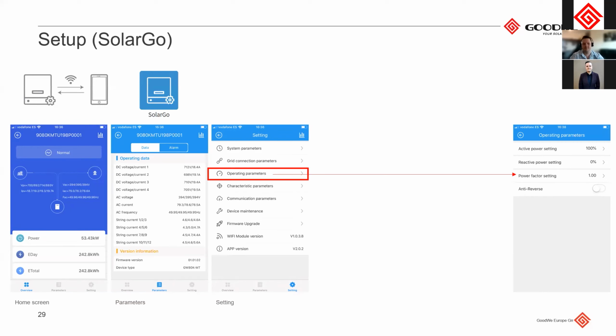Then you'll see we also have the power factor settings, the reactive power settings, the anti-reverse settings. So this is the export power limit. Normally we won't enable the export power limit on our inverter because it's only if you are using a single inverter with a smart meter. But for most commercial installations, the smart meter just won't do because the amp rating for the CT currents is only 120 amps, and the conductor size is very small. So that normally rules it out, and that's why we use the SEC1000. So we do not enable this anti-reverse or power limit on the inverters itself, because that will be controlled by our device externally.